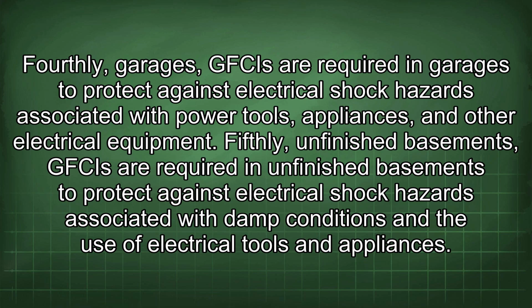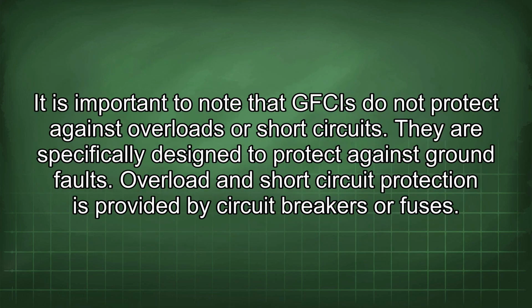GFCIs are required in unfinished basements to protect against electrical shock hazards associated with damp conditions and the use of electrical tools and appliances. It is important to note that GFCIs do not protect against overloads or short circuits. They are specifically designed to protect against ground faults. Overload and short circuit protection is provided by circuit breakers or fuses.